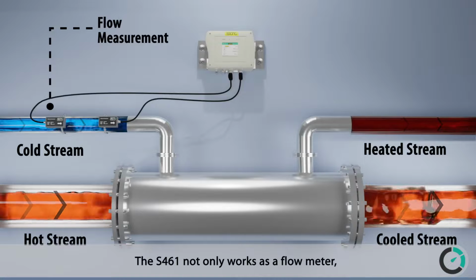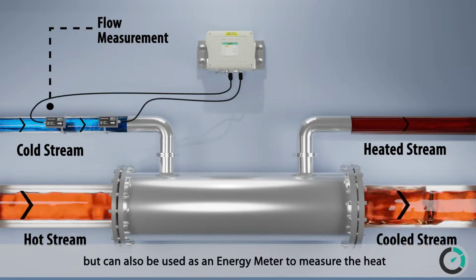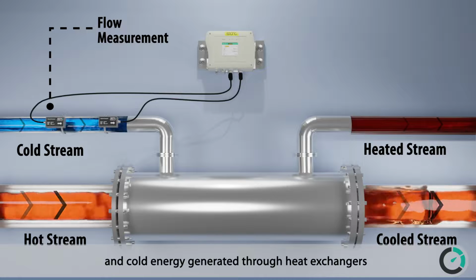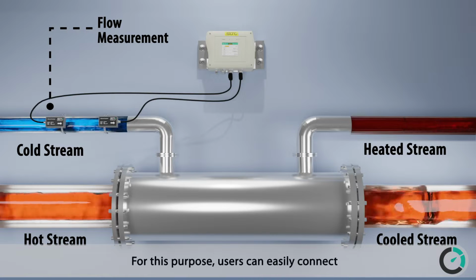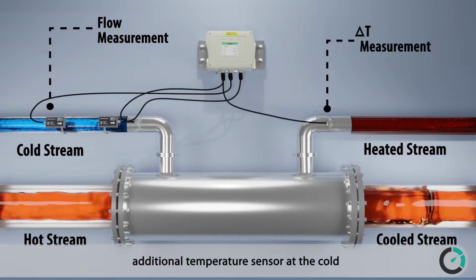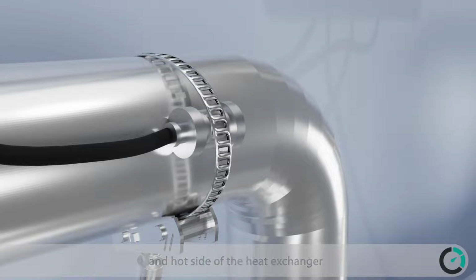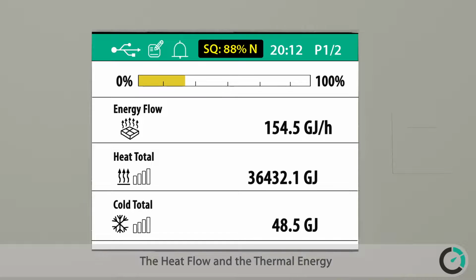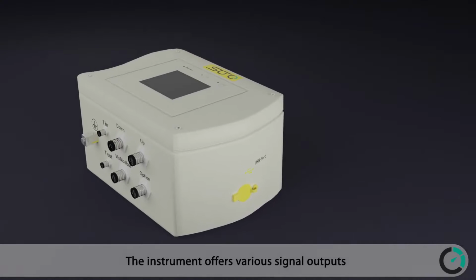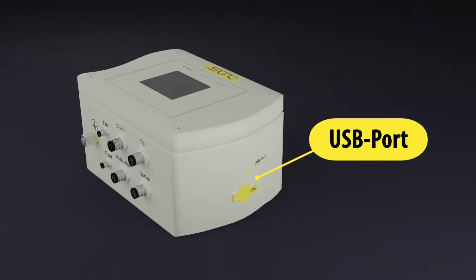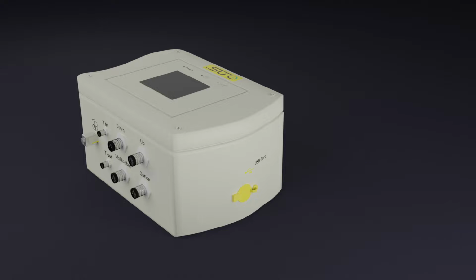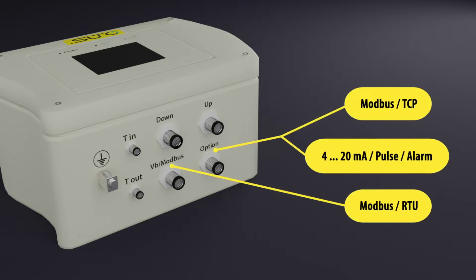The S461 not only works as a flow meter, but can also be used as an energy meter to measure the heat and cold energy generated through heat exchangers. For this purpose, users can easily connect additional temperature sensor at the cold and hot site of the heat exchanger. The heat flow and the thermal energy are calculated automatically and displayed on the screen in the SUTO app on any smartphone. The instrument offers various signal outputs: USB port, Modbus TCP, 4 to 20 mA pulse and alarm, Modbus RTU.